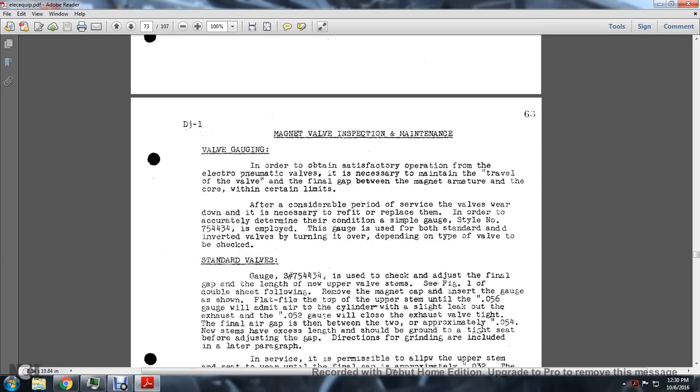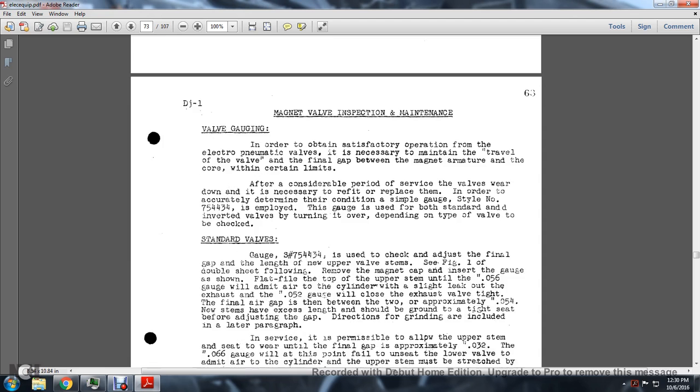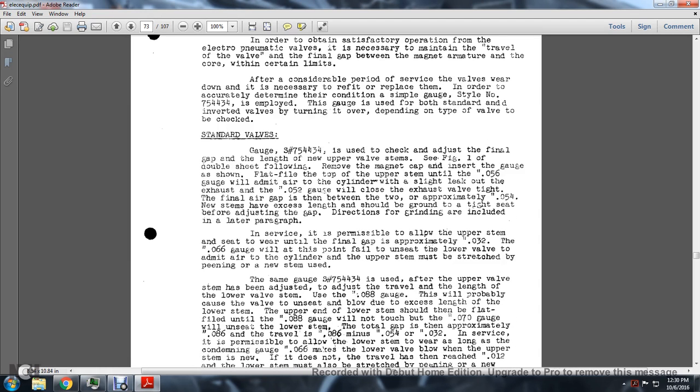Magnet Valve Inspection and Maintenance - Valve Gauging: In order to obtain satisfactory operation of the electropneumatic valve, it is necessary to maintain the travel of the valve and the final air gap between the armature and the core within certain limits. After considerable service, worn valves must be refitted or replaced. To accurately determine the condition, a simple gauge of style number 754434 is applied. This gauge is used for both standard and inverted valves, turned over depending on the valve type.